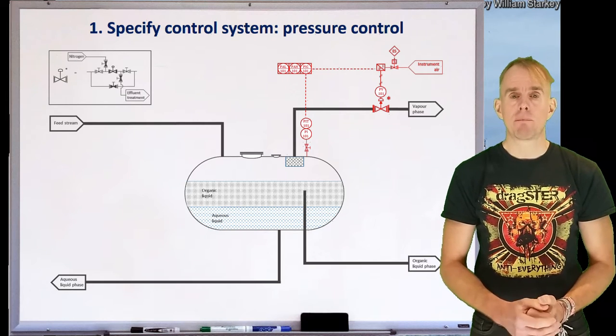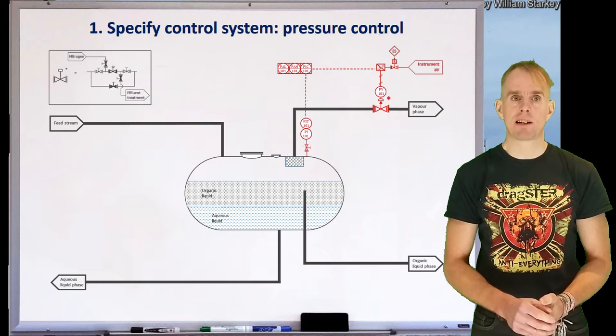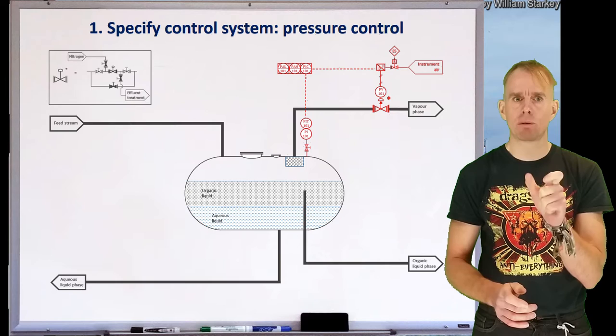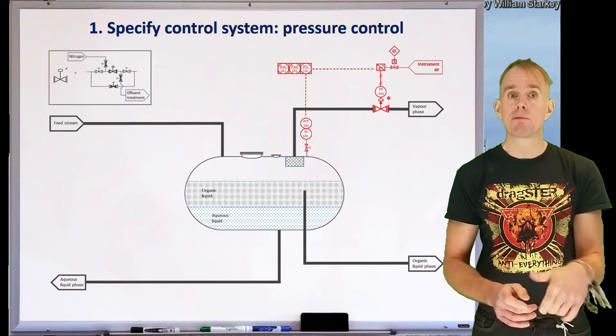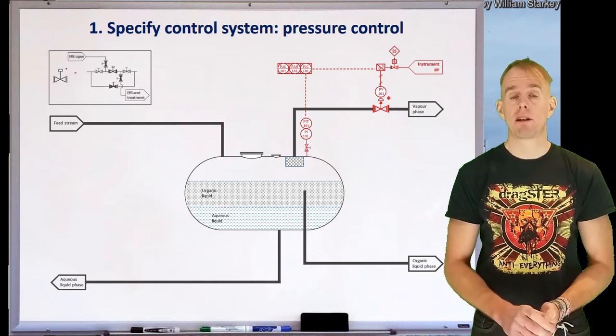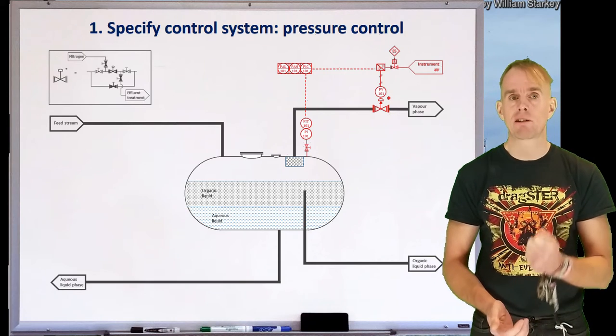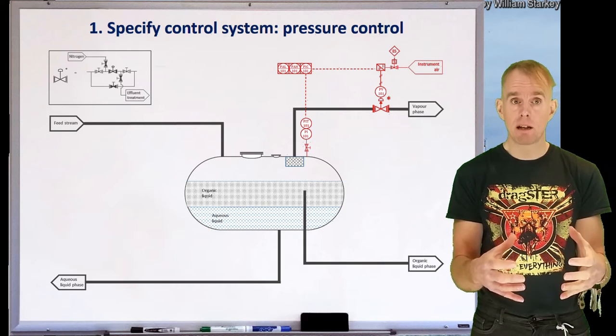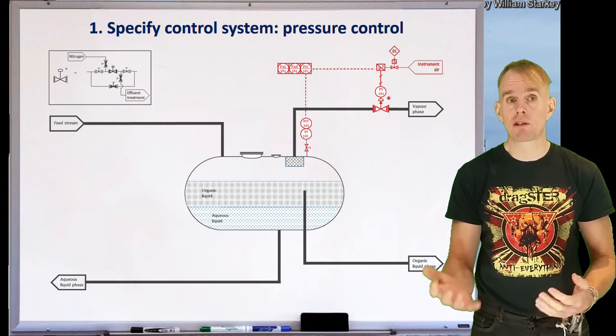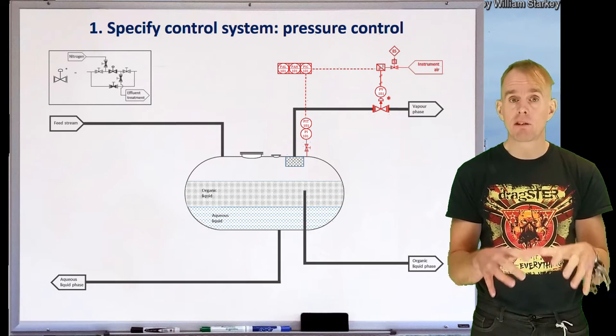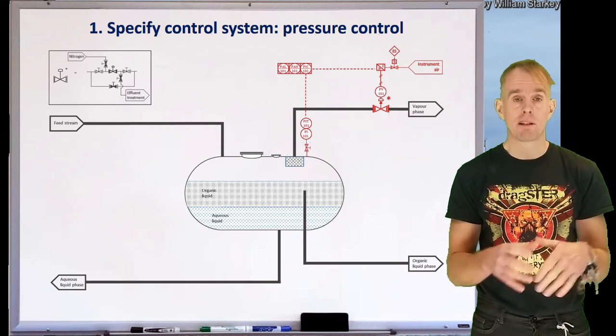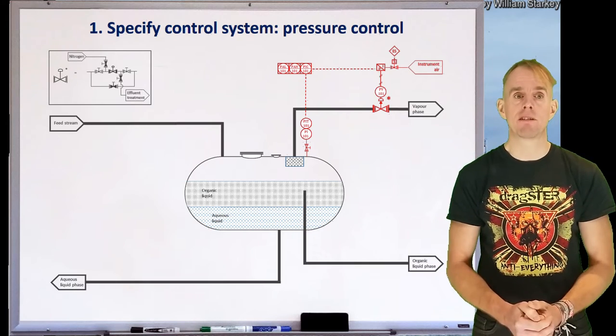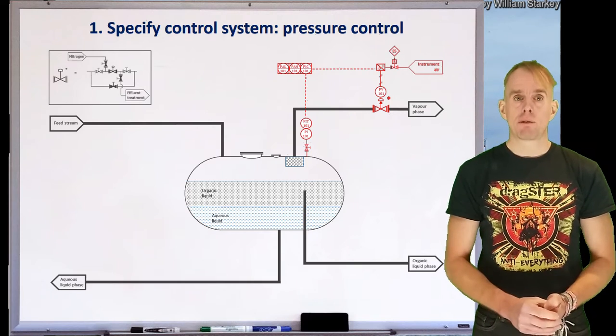Also on this diagram we have a connection into the emergency shutdown system. The diamond marked 'ES' is emergency shutdown, and it connects directly to a solenoid valve on the instrument air, which may fully open or fully close that instrument air supply depending on what we want the shutdown condition to do — we may want to box the vapour in or allow all the vapour to escape. What exactly happens is specific to the design and can't be stated generically without knowing the process in more detail.